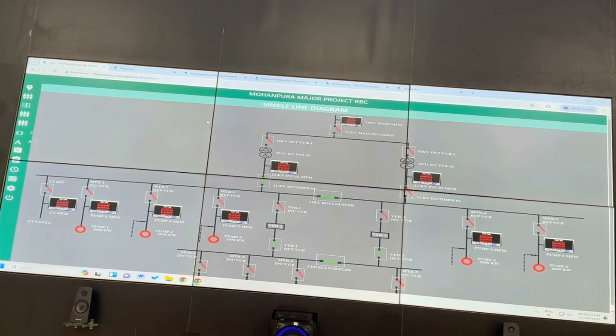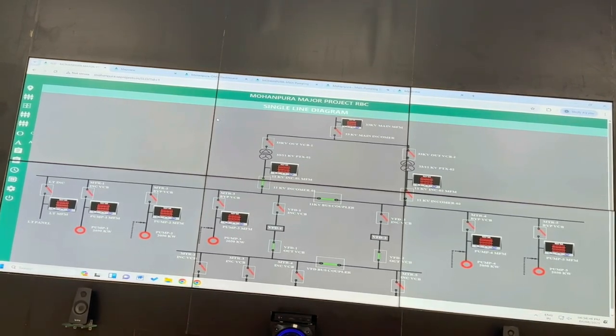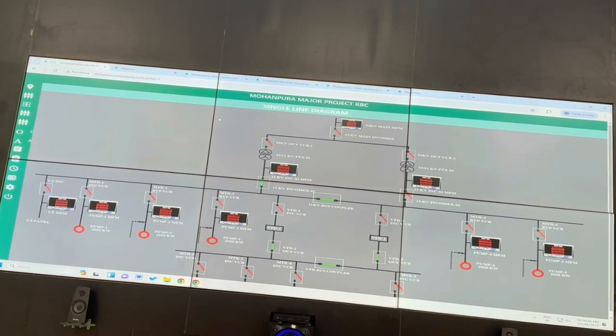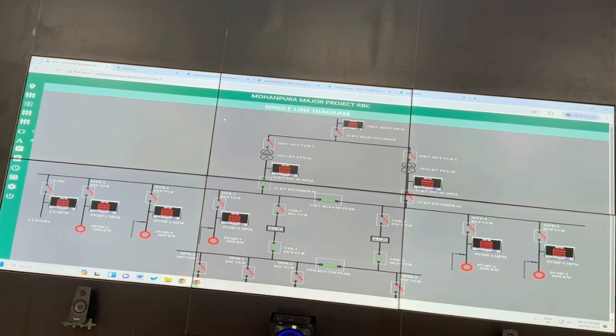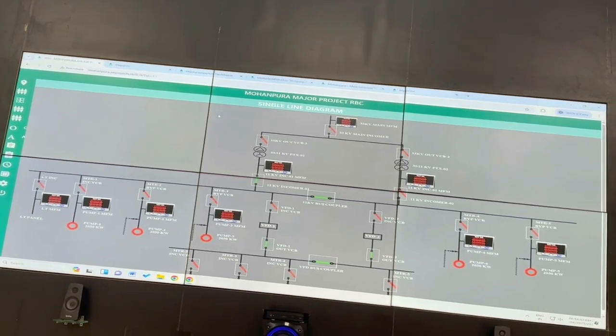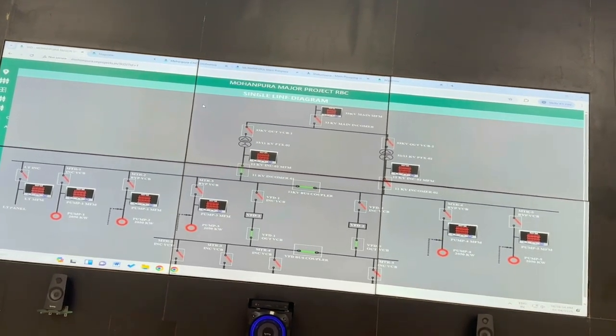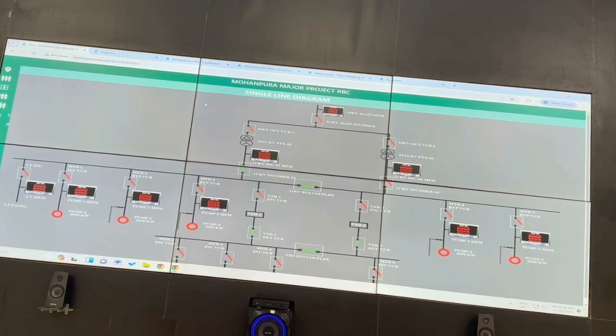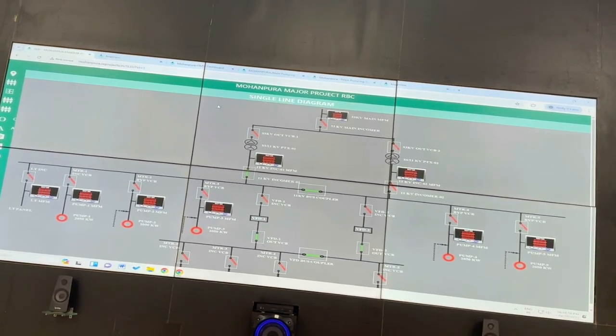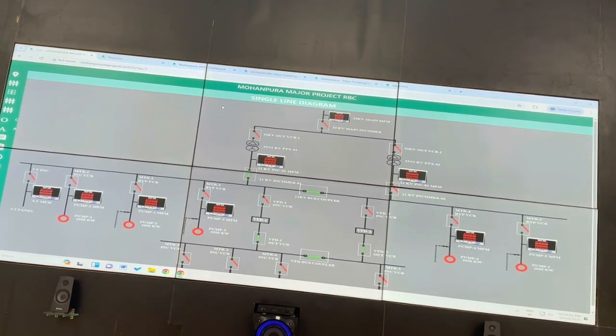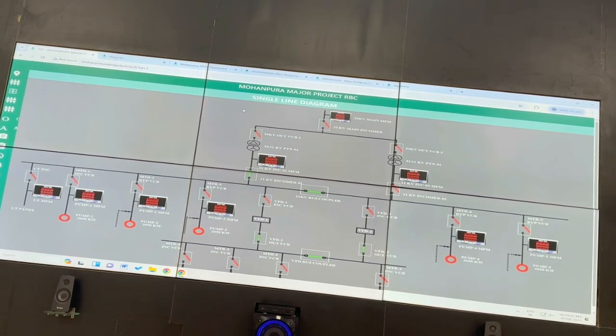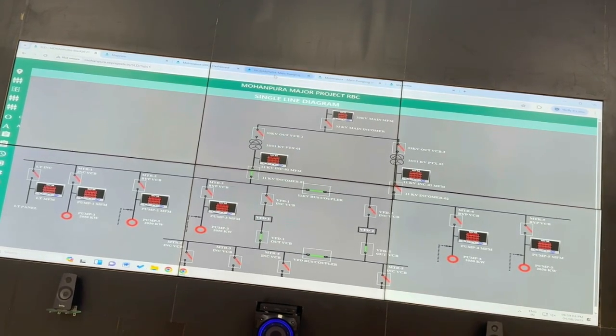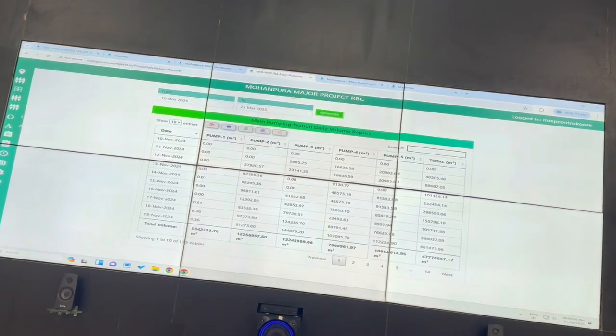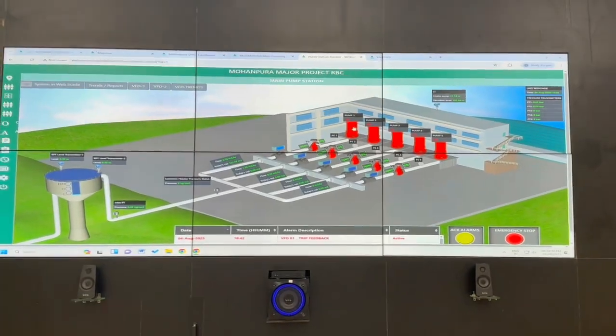Now we can drill down to individual details. We can see all the details of each pump with different parameters, electrical parameters for monitoring, how much power is flowing to each part, reactive power, active power, power factor, etc. What's the demand of energy based on all these things? Backend logic is set. Any parameter, if it's violated, there will be an alarm or alert generated.